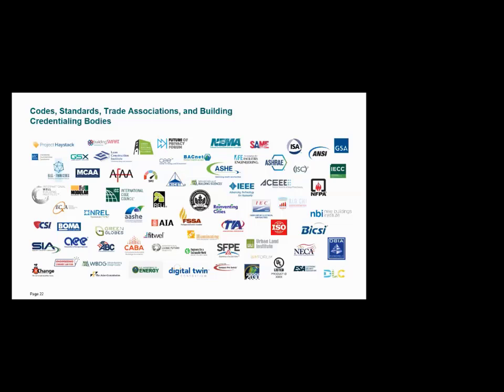NFPA has a standard for integrated fire protection and life safety system testing. This is effectively a recommissioning type of standard, and it's now required in the 2021 IBC/IFC, which calls for NFPA 4 recommissioning where you have smoke control or high-rise buildings. So think about your smart buildings - you have tenant retrofits going on, and you really need to do some of this to make sure the original sequences are still working, still operational.